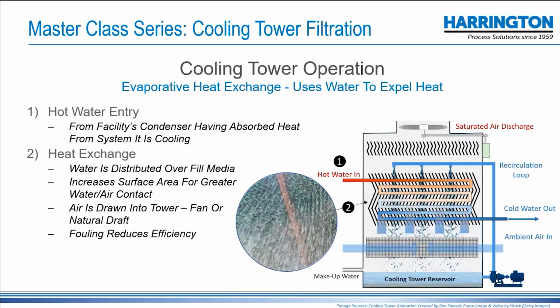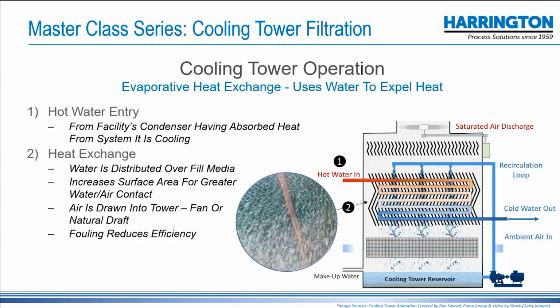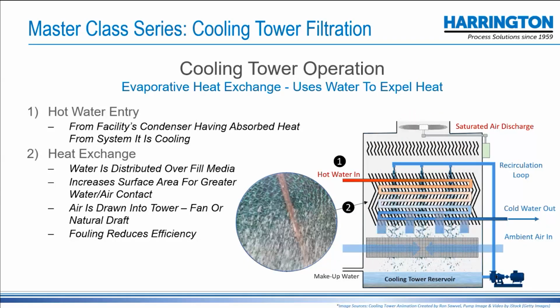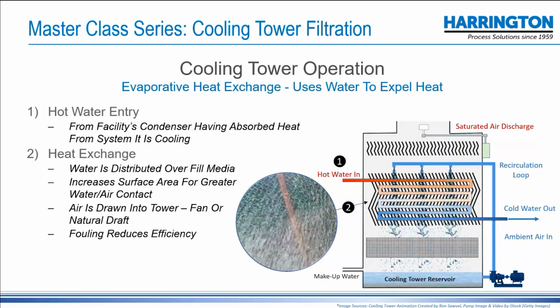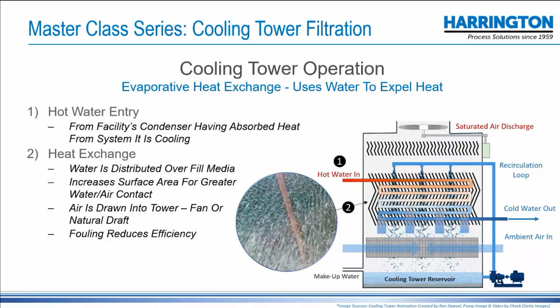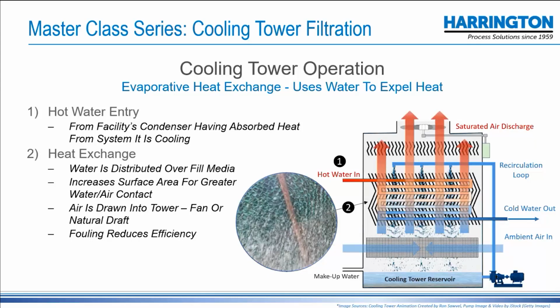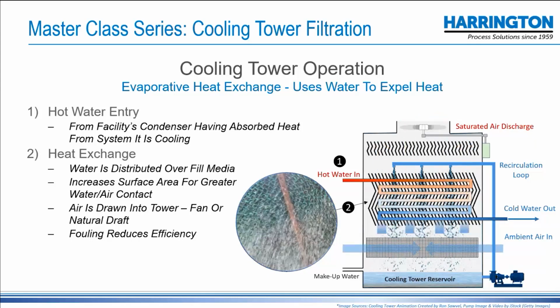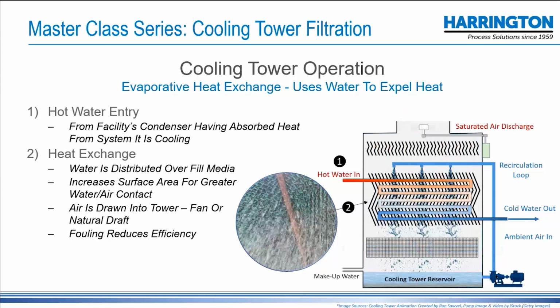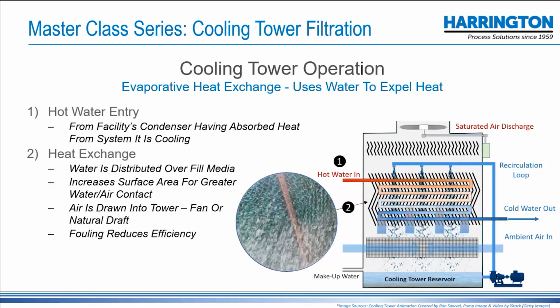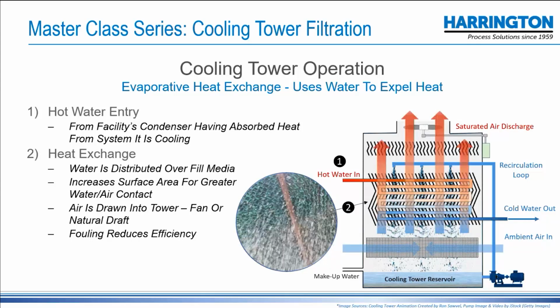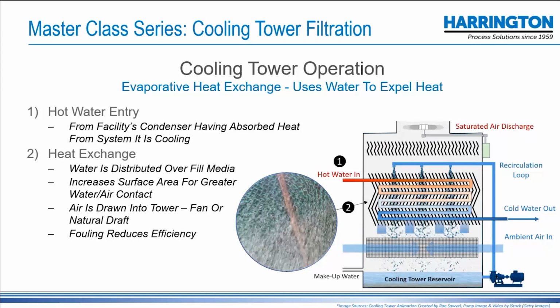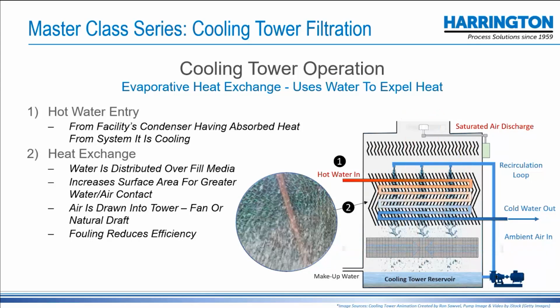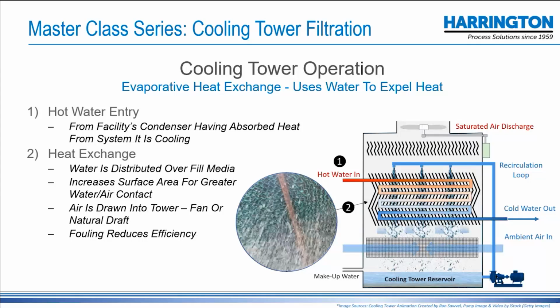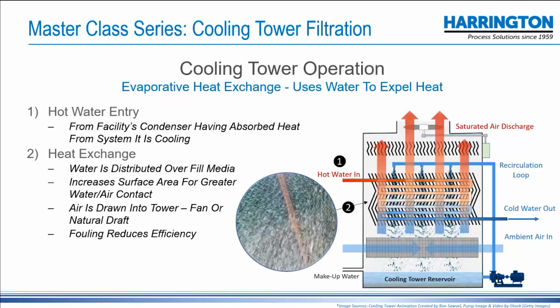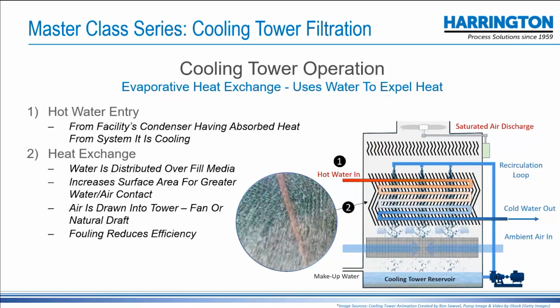And that video that's playing is an actual element. There are different kinds. There are honeycomb elements. What you see here is corrugated plates that are basically just creating more surface area so that the air has more opportunity to cause evaporation on the water itself. So if that becomes plugged, if it gets covered in some form of dirt, you lose cooling efficiency, and so you lose the very purpose why that cooling tower is there in the first place.